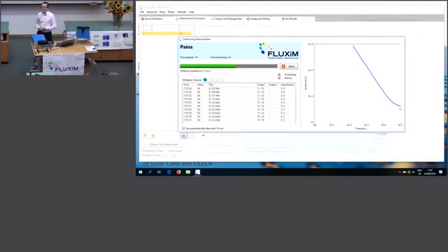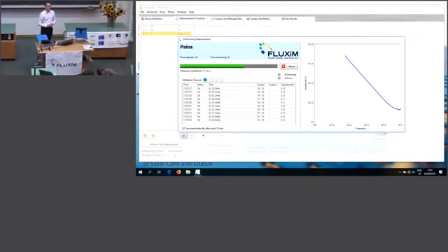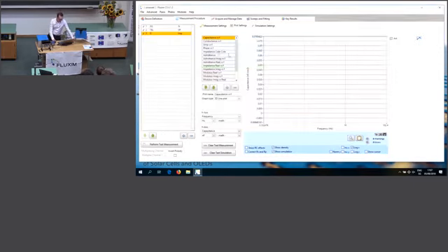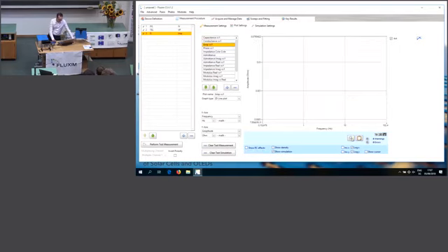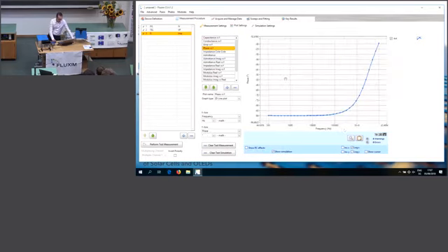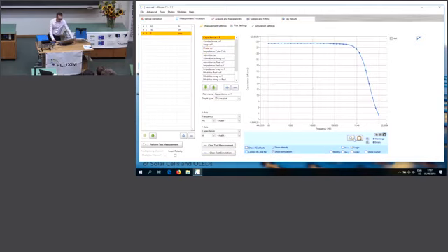With PAIOS we can go down to 10 millihertz, maybe even 1 millihertz, but we have never tried because, as you can imagine, already 10 millihertz takes a while, so you need to measure it over the weekend. But we are capable of going to very low frequencies. Now we can look at the amplitude or the phase. In this case, it's apparently a device where not much happens. The capacitance is quite flat, so there's no sign of traps. When we apply an offset voltage, we would probably see a different level.